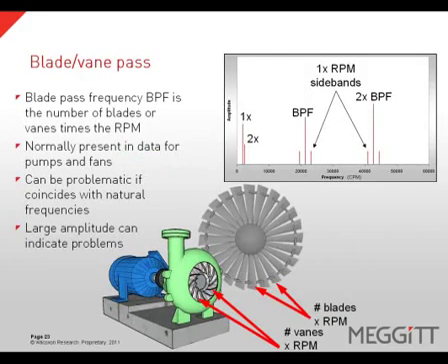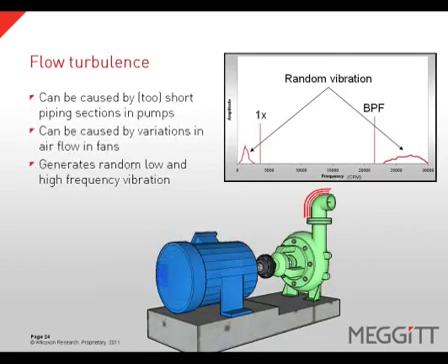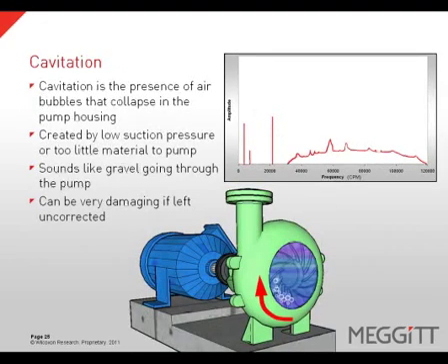Blade or vane pass frequency is the number of blades or vanes times the RPM of the machine. This frequency is normally present in data for pumps and fans and can be problematic if it coincides with natural frequencies of the system. Large amplitudes of these frequencies can indicate a problem. Flow turbulence can occur in both pumps and fans — with pumps, turbulence can be created by piping sections that are too short; with fans, it can be caused by variations in airflow. Flow turbulence generates random low and high-frequency vibrations. Cavitation is the presence of air bubbles that collapse in the pump housing, created by low suction pressure or too little material to the pump. It sounds like gravel going through the pump and can be very damaging if left uncorrected.